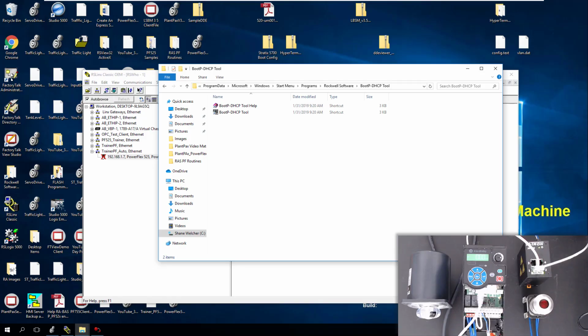All right, so in this video, what we're going to show you is how to use BootP server to set your IP address to your Powerflex 525 drive. And just know we're going to do this in the most streamlined process ever.